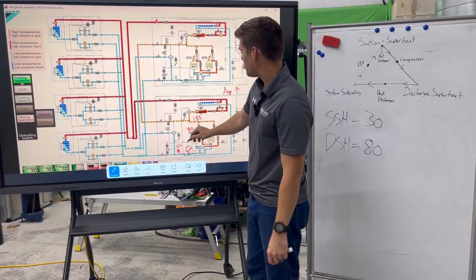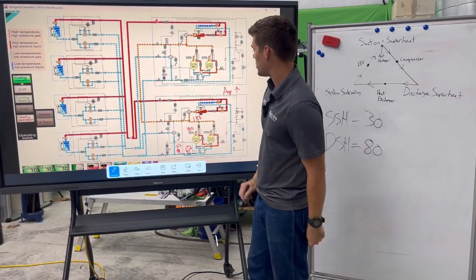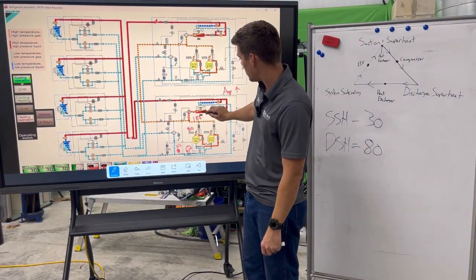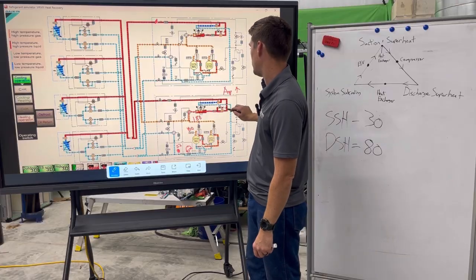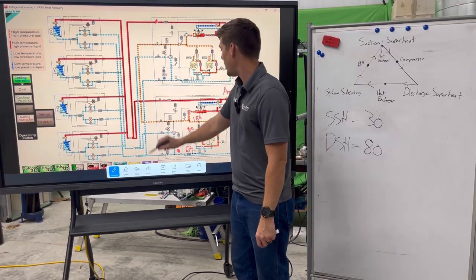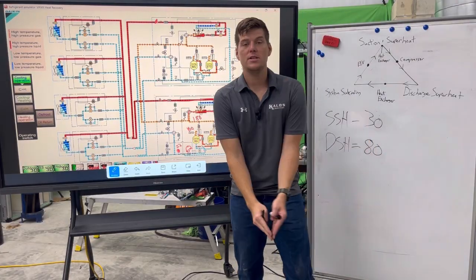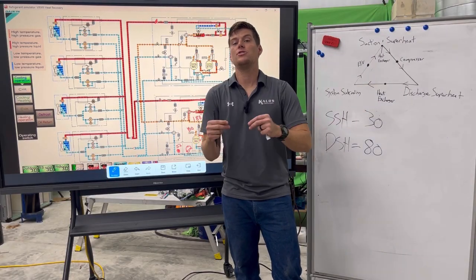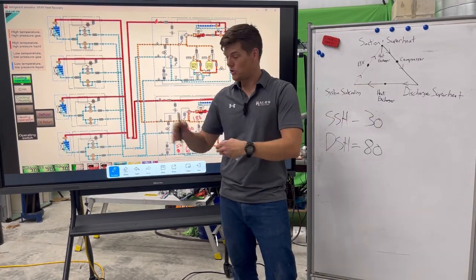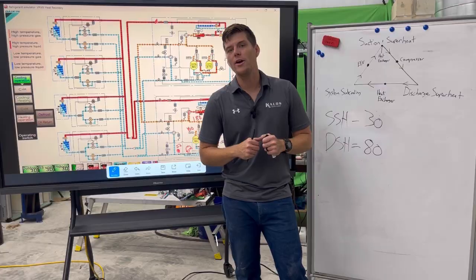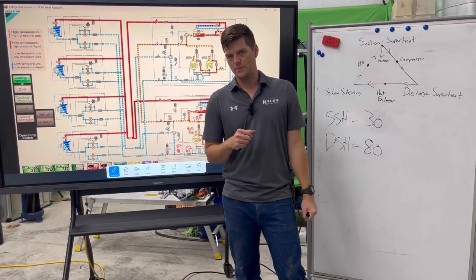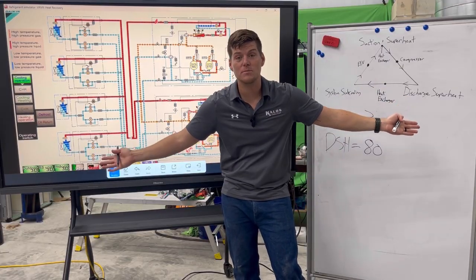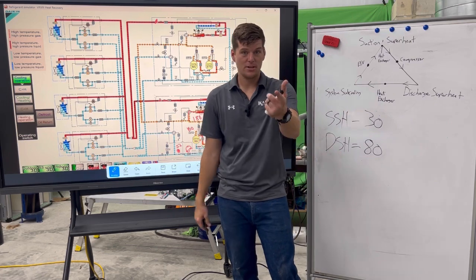So now that we've got our suction superheat and our discharge superheat, what's going to happen next? Well, that hot gas is going to come up here and it's going to go through our heat exchanger and it's going to do what? It's going to turn into a liquid, right? And then we have a choice. And the choice is, are we going to measure suction? We measure suction superheat. We measure discharge superheat. Do we know where to measure system subcooling? Where do we measure system subcooling? That's the question I'm asking you.